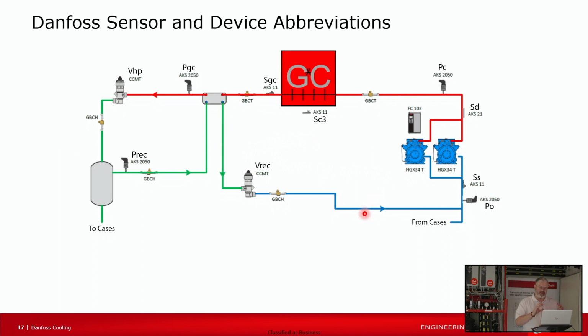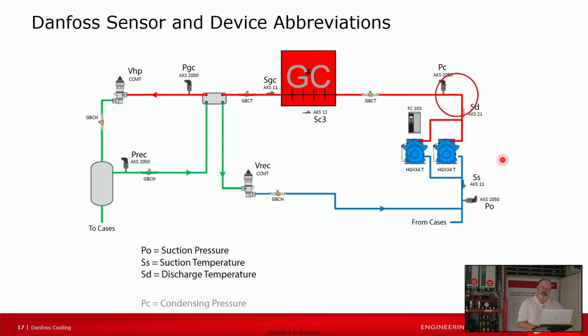So this is a basic overview of our medium temp transcritical system. Let's look at the sensor abbreviations. I get a few complaints that they're confusing, but I think if you hear the logic, they make perfect sense. The first one we'll look at is the suction pressure. Most people are used to seeing that called SUCT-PSI. For us, the P represents a pressure transducer. The O represents outlet of the evaporator. So our line coming back from the cases, we want to know the pressure leaving the evaporator. So that's pressure outlet. Then we go up. The uppercase S means it's a temperature sensor, and it's on the suction line. Temperature sensor on the discharge line. Pressure transducer on the line to the condenser.